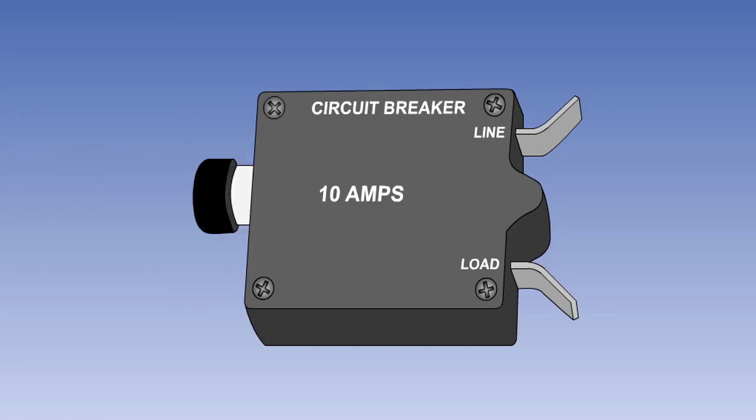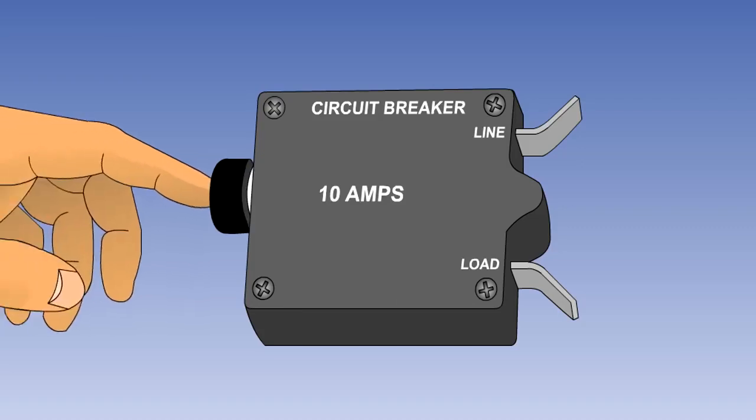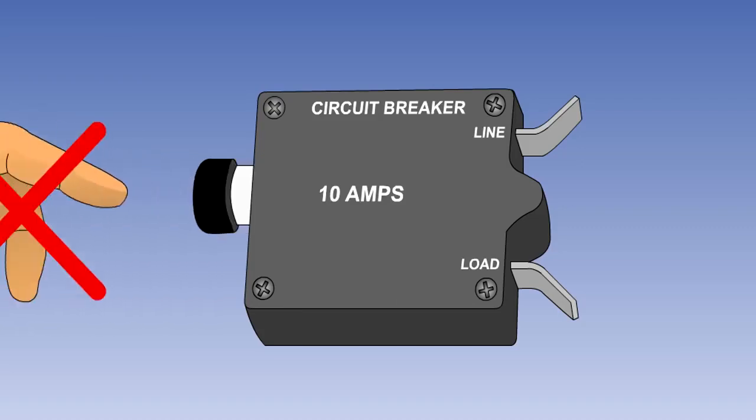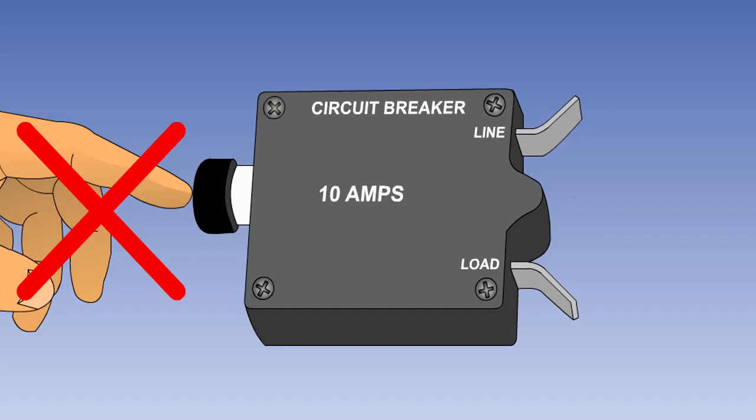Circuit breakers can be tripped and reset any number of times, but remember that a tripped circuit breaker should only be reset once. If it trips again, the fault must be dealt with before another reset attempt is made.